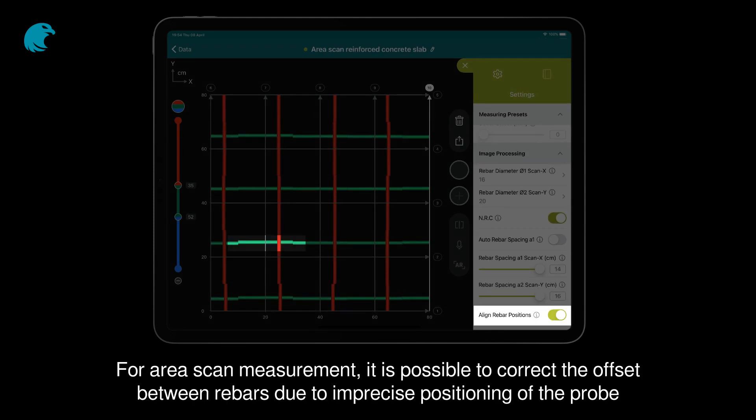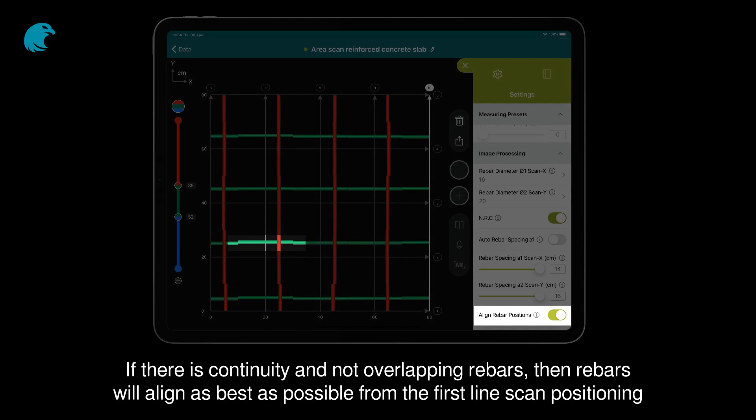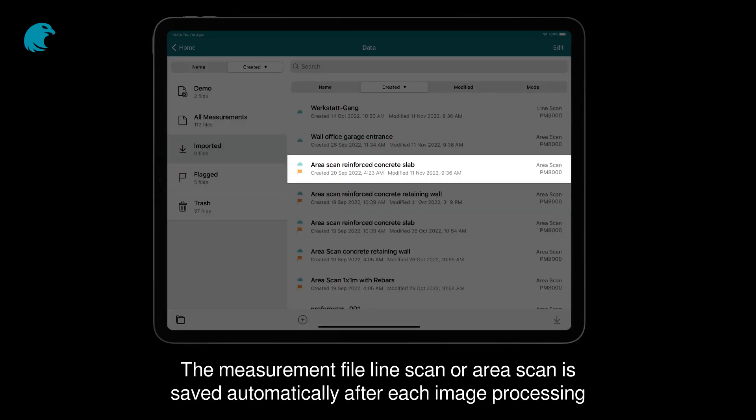For area scan measurement, it is possible to correct the offset between rebars due to imprecise positioning of the probe. If there is continuity and no overlapping rebars, then rebars will align as best as possible from the first line scan positioning. The measurement file — line scan or area scan — is saved automatically after each image processing.